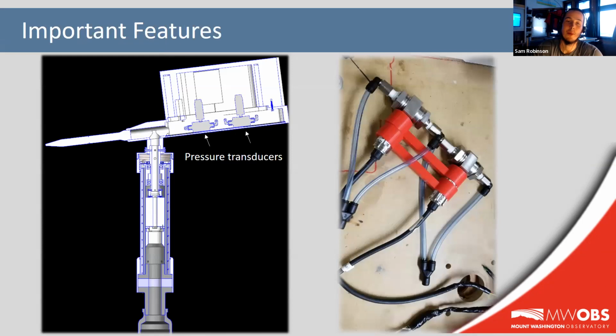So now we're going to be jumping into even greater detail here. Here are some of the more important design details really targeted at those three main improvements that we were looking to achieve. So first off is the use of two pressure transducers, a 0 to 10 inch pressure transducer and a 0 to 7 inch pressure transducer made by the company Omega Incorporated. This isn't necessarily unique to Pitot 22.